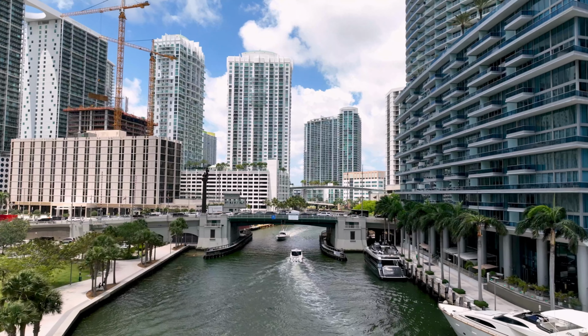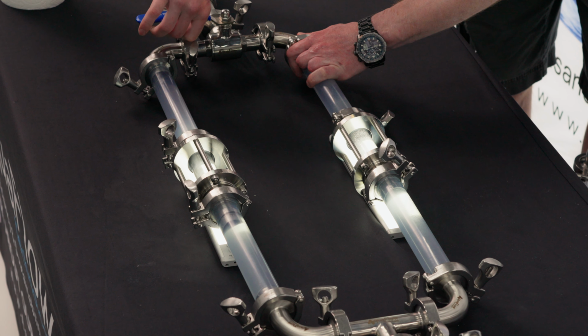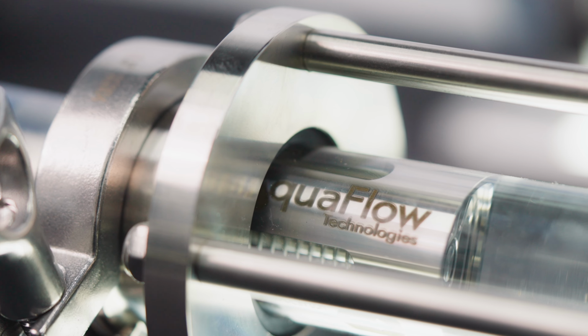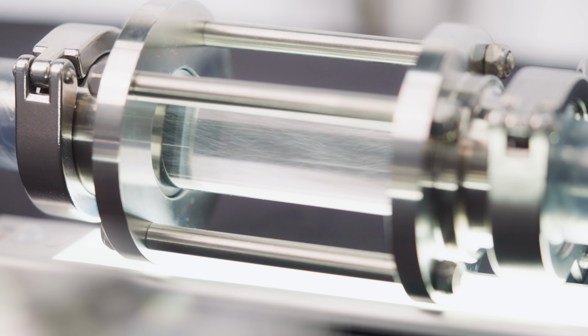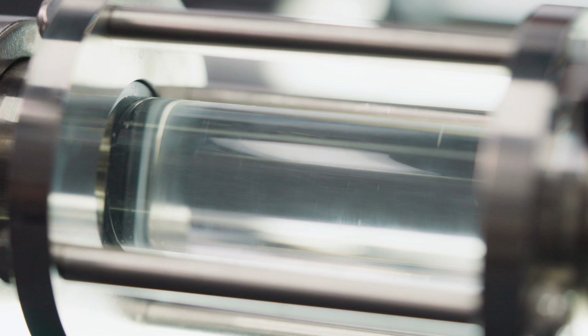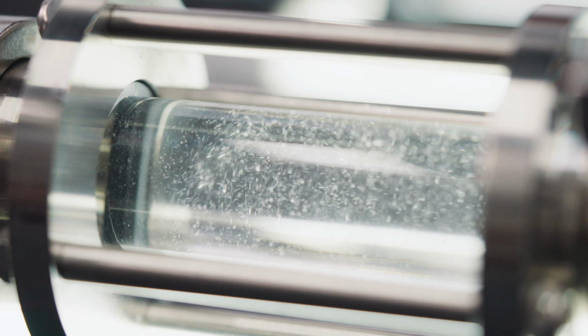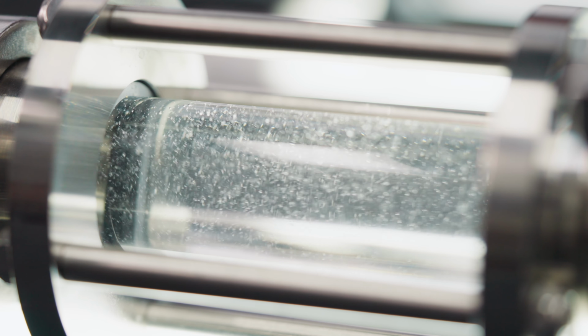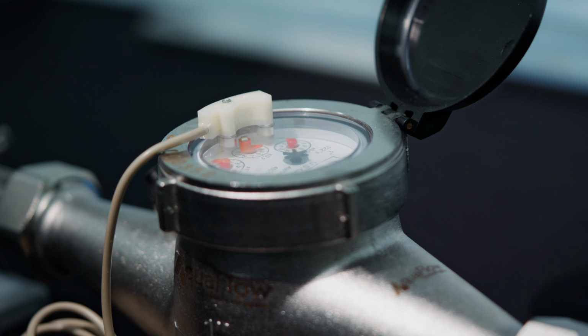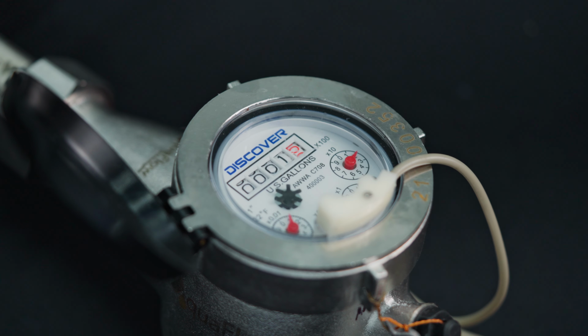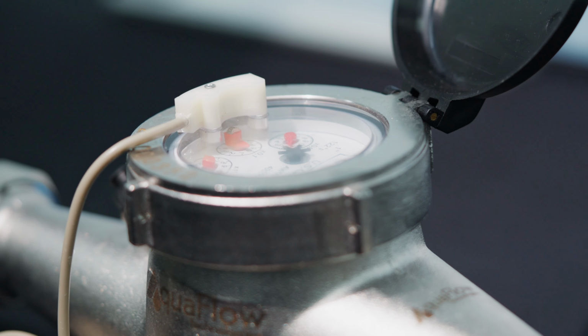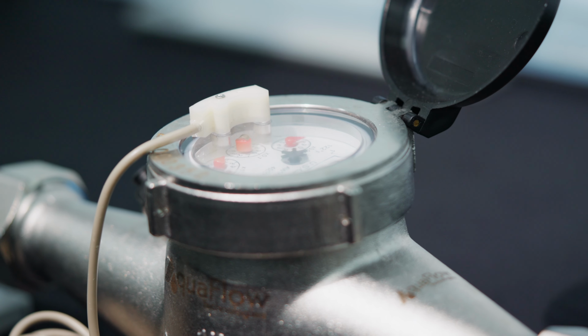We are here at the manufacturer in Miami, Florida, and we have our demo set up. What you're seeing right now is a demonstration of how water flows through typical industrial and residential piping configurations. Water normally will flow in a turbulent flow. You can see the turbulence in the flow here, along with carrying in trapped air bubbles. These air bubbles are metered the same as water. The meter cannot determine the difference between air and water and measures all volume the same. The impact of turbulent flow makes your meter over-register.